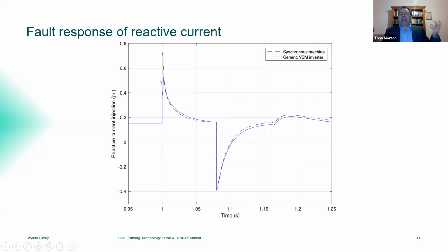And we can also look at the reactive current response to the fault. And again, we can see that even though our generic grid forming inverter does have a current limiting behaviour, so the fault current doesn't peak at the same instantaneous level that we see for the synchronous machine, nonetheless, it's a very similar fault current behaviour that we see, subject to that limiting. And the stabilisation of the system, it seems, does not critically depend on the peak magnitude of this fault current. So even though we don't get, and we don't expect to get, the same level of maximum fault current contribution from power electronics that we get from passive synchronous machines, nonetheless, we can still expect them to make a similar contribution to the stabilising behaviour of the system.